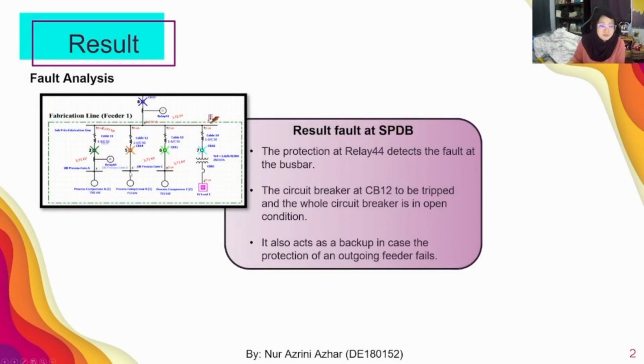For the next part, I'll proceed with the result of the fault at SPDB, which is the sub-primary distribution board. As you may see, the fault occurs at the end of the bus bar, and relay 44 will detect the fault, and CB12 will be tripped, and circuit breakers 2, 5, 6 and 7 will be in open condition. So it may also act as a backup in case the protection of an outgoing feeder is failing.